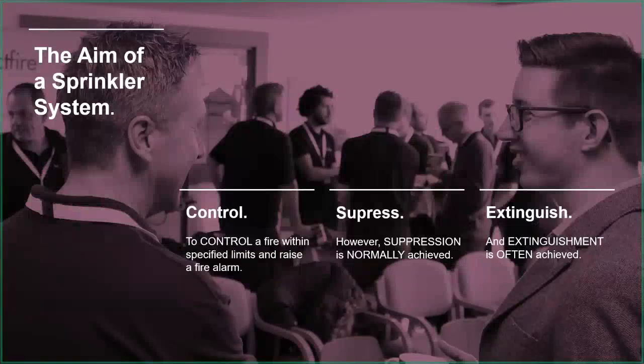However, suppression is normally achieved, so we can make the fire smaller and more manageable, so when the fire and rescue service arrive they've got a lot less to deal with. They'll be pleased the fire has been controlled and contained to a particular area, but even better if it's suppressed. Extinguishment is often achieved, but it's good to point out that the aim of a sprinkler system is not to extinguish the fire. If it does, that's a bonus, but sometimes people are disappointed if the sprinkler system doesn't completely extinguish the fire - that's just not its primary purpose.